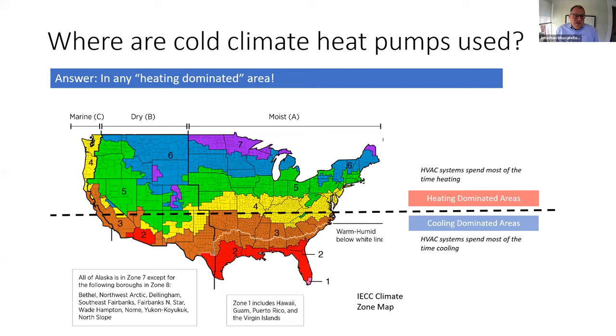And I have found through my experience living and working in climate zone 4 that we love using cold climate heat pumps, because they are purpose-built to make heating comfort and be easy to operate in inclement weather. And when you look at the black line that I drew on this map, it's this long-standing heat pump business rule that above that line, roughly, more of the equipment hours of operation in a year are spent heating. We call that in the HVAC industry a heating dominated area or climate. And in my mind, anything above that dotted line, certainly in climate zone 4, is probably a great location for a cold climate heat pump. Not because you absolutely need it, but because it's going to give you so many of the features, benefits, and comfort aspects that will give you a great experience with a heat pump.